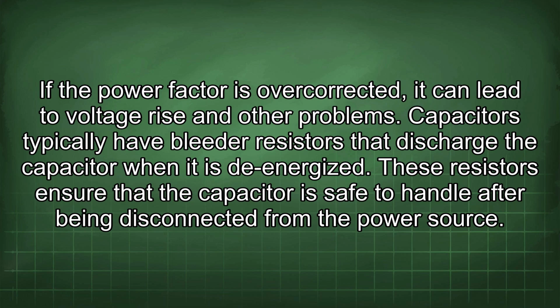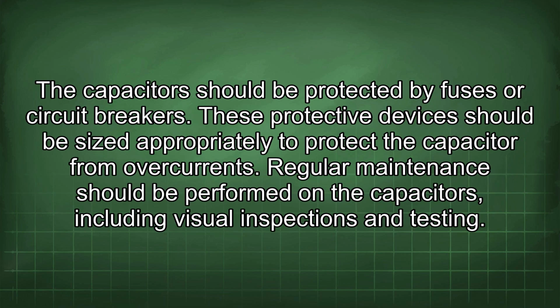Capacitors typically have bleeder resistors that discharge the capacitor when it is de-energized. These resistors ensure that the capacitor is safe to handle after being disconnected from the power source. The capacitors should be protected by fuses or circuit breakers. These protective devices should be sized appropriately to protect the capacitor from overcurrents.